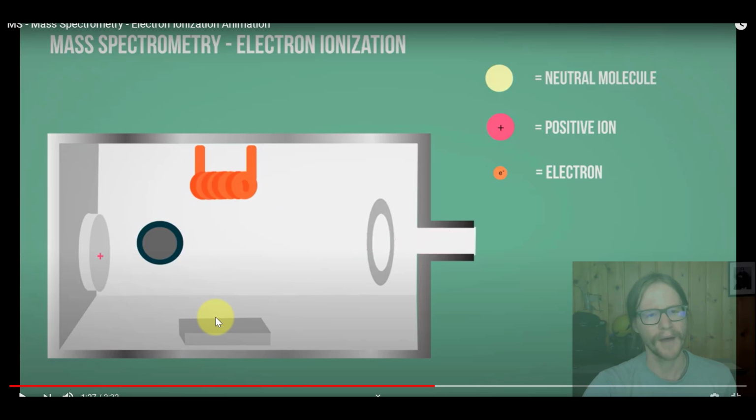And that's an important part about mass spectrometers. I didn't list it as a component, but it really is an honorary fourth component, because virtually all mass spectrometers have some part of the system that's under vacuum. And so vacuum pumps are integral to the functionality of most mass spectrometers.